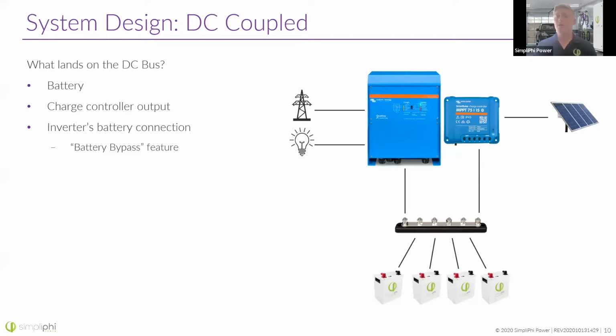If you have 80 amps coming in from your PV array and 80 amps going out to your loads, I would really take the time to put an amp clamp on your battery bank wires and check how much power is going in and out of them. It should be very, very close to 0 amps in that scenario. And it is, it's what I've seen happen. So your DC bus bar already allows power to bypass the battery bank without charging and discharging those batteries rapidly. And this is the DC bus bar that I'm talking about.